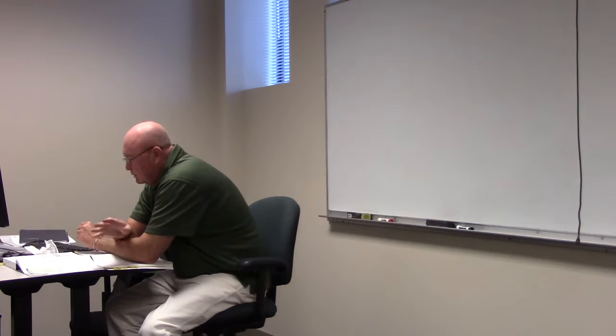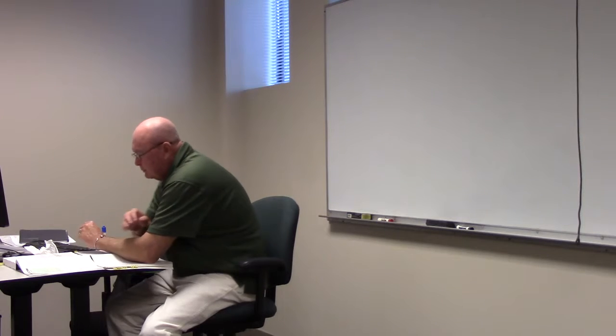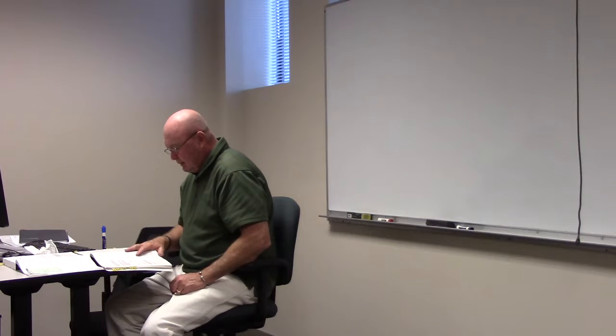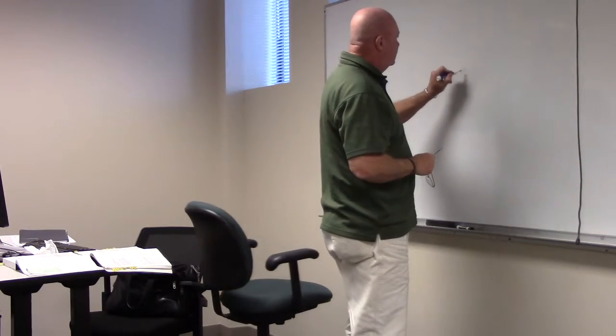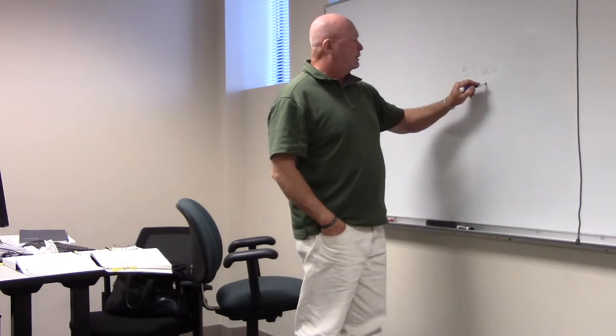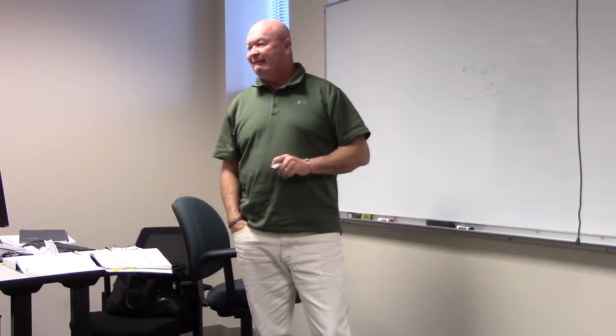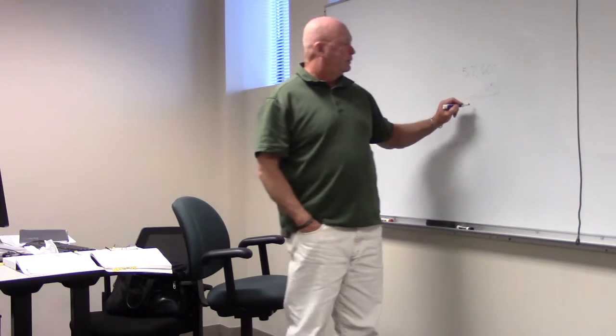So let's look at this example. Suppose we got a warehouse, 57,600 square foot. Let's go to our table and find warehouse and tell me what we're going to do. First 12,500 at 100%. No, we ain't gonna do that yet. We gotta go to 220.12 and find out what our lighting load is first, based on a warehouse. We've got 57,600 square foot, and for a warehouse in that table, what is the lighting load multiplier? 0.25. So do the multiplication and tell me what you get. 14,400. Yep, 14,400.